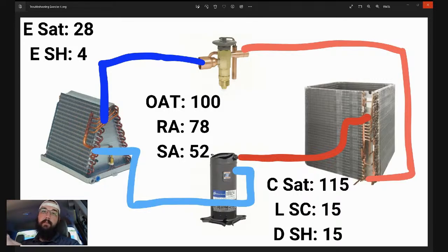It's hard when you get a coil that's impacted. It's actually internal to the coil to get that to flush back out of there without pulling it and without getting some kind of actual pressure on it. A pump up sprayer can help. If you can put hot water in your pump up sprayer, a lot of them don't do well with that. At the same time, by the time the water gets all the way through the pump and then sprays onto the coil, it ends up cooling off enough to where you lose the effect of the hot water. It may be quite warm water by the time it's coming out of your sprayer, but it's not hot. And my objective here is I want legitimate hot water hitting that coil to try to just flush some of that out.